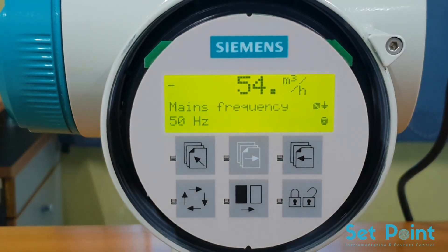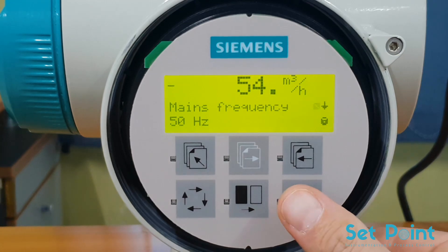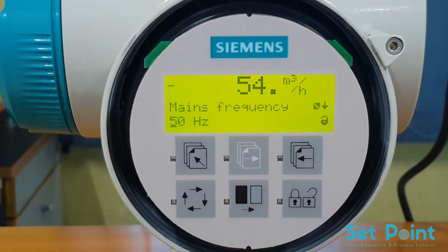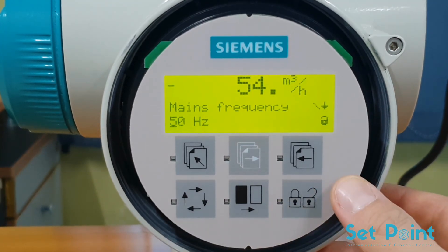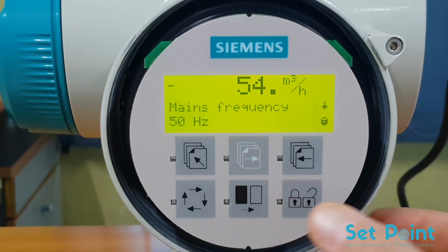Press the lock/unlock key. The first parameter is mains frequency. If necessary, press the lock/unlock key to edit the parameters. Press the change key to change the mains frequency from 60 Hz to 50 Hz. To save this value, press the lock/unlock key.